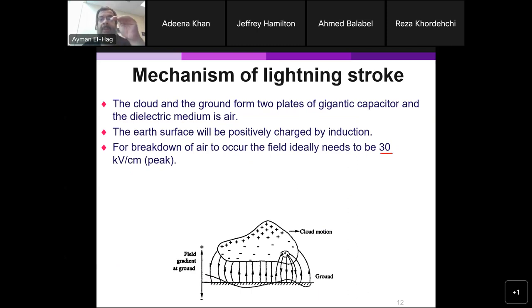Okay, now remember this is a surge. So here we don't talk about RMS. RMS is only for AC, a sinusoidal. For AC, the breakdown of air is 22 kilovolt per centimeter. But here we talk only about the peak value, which is 30 kilovolt per centimeter.